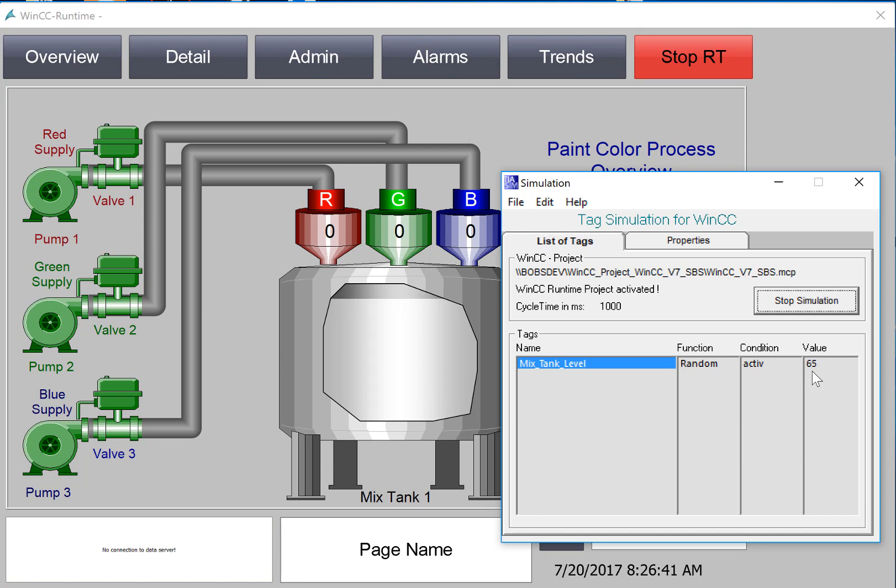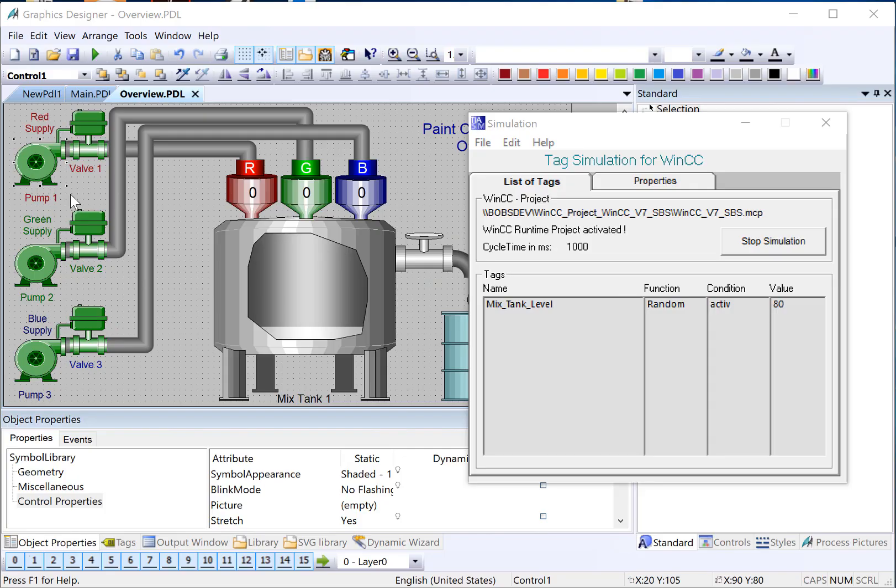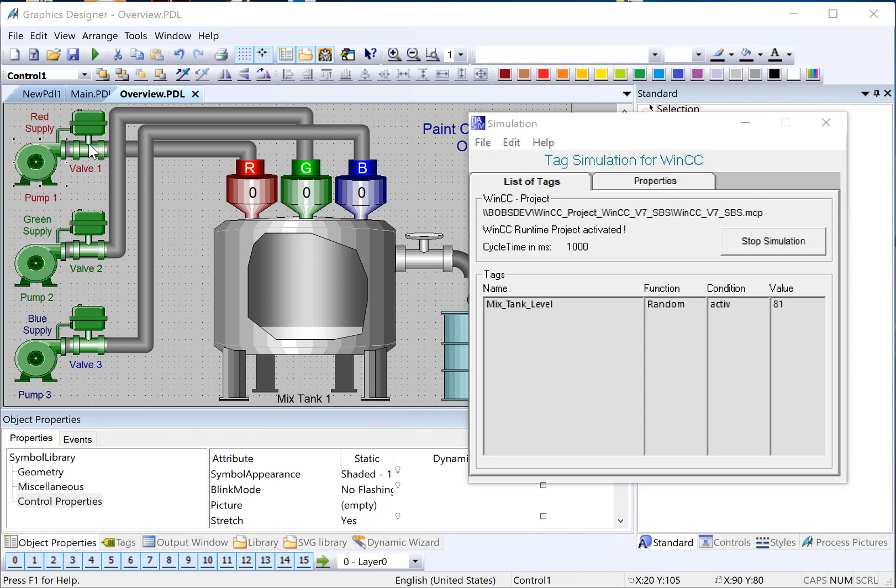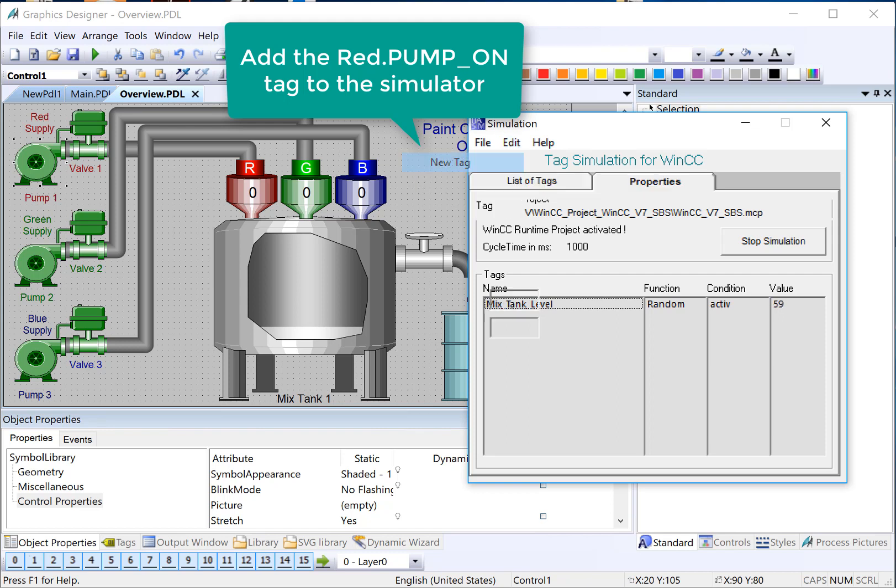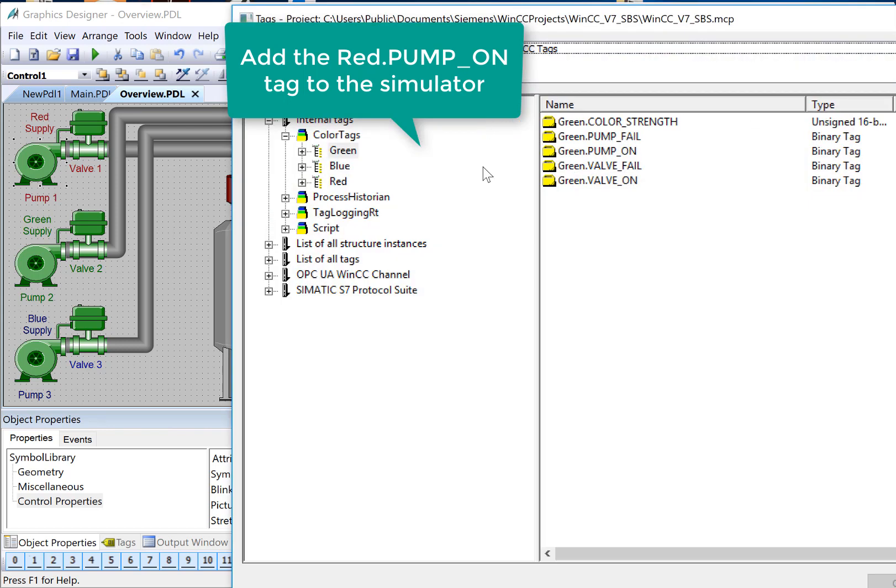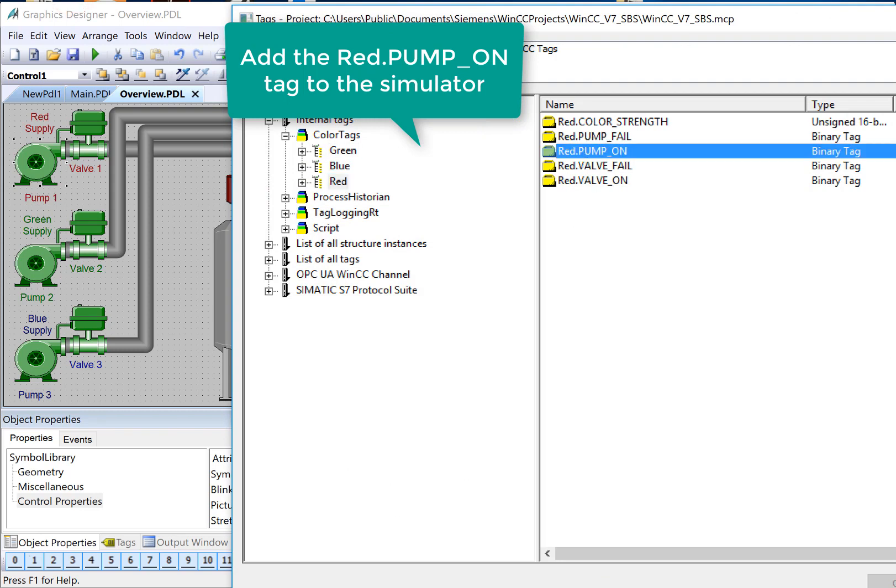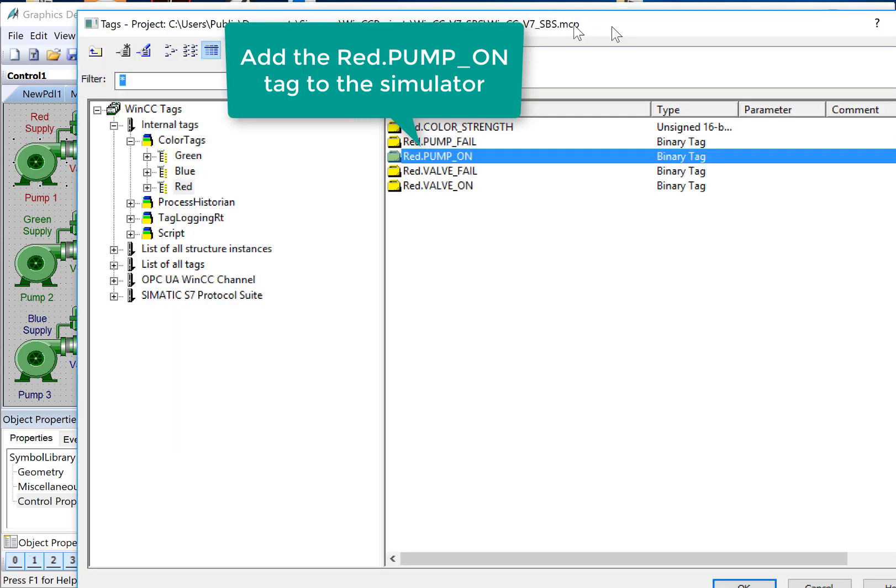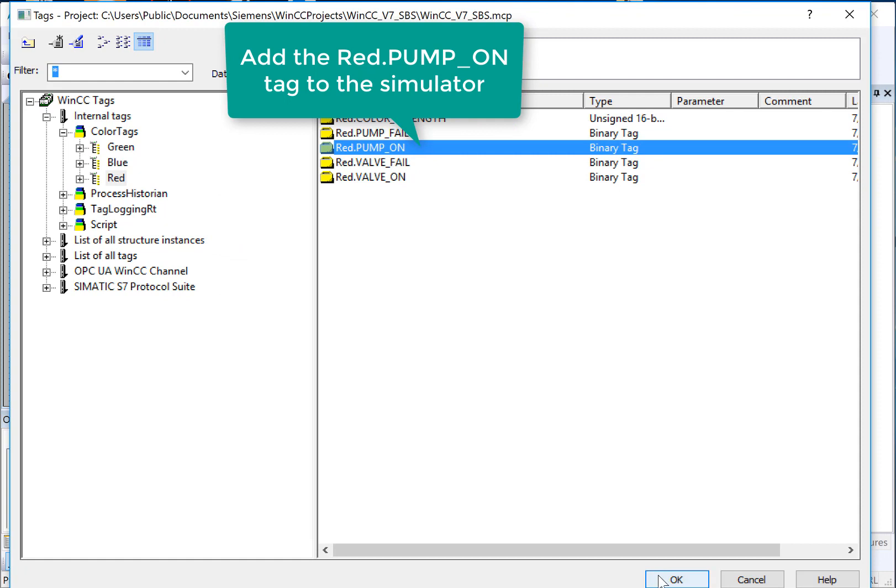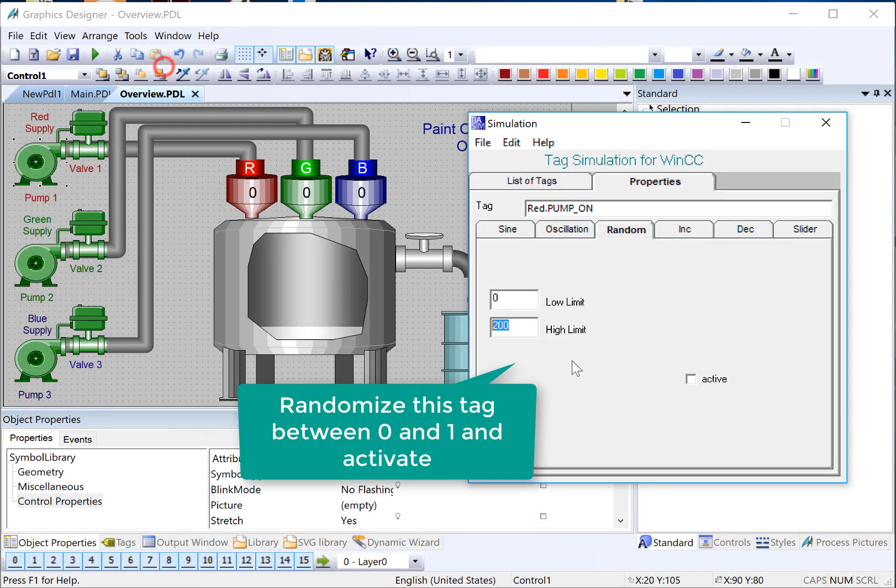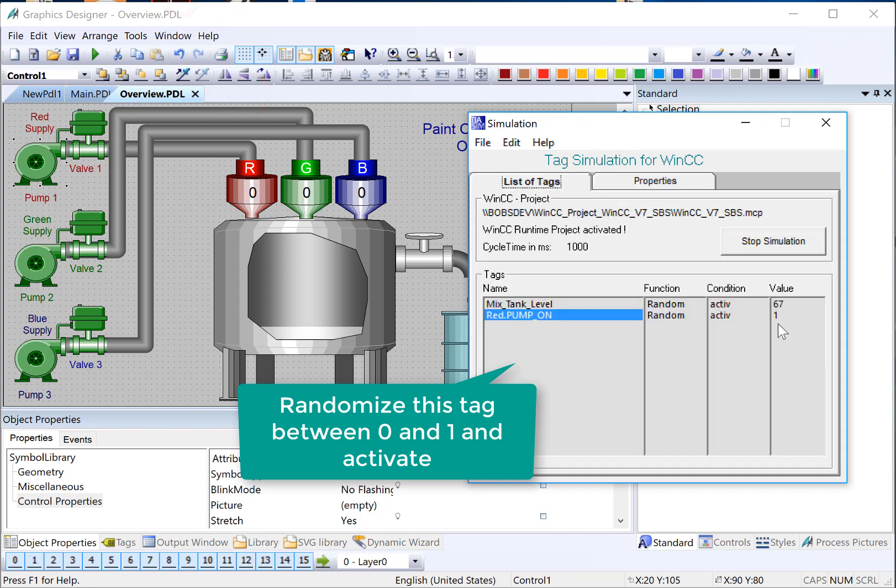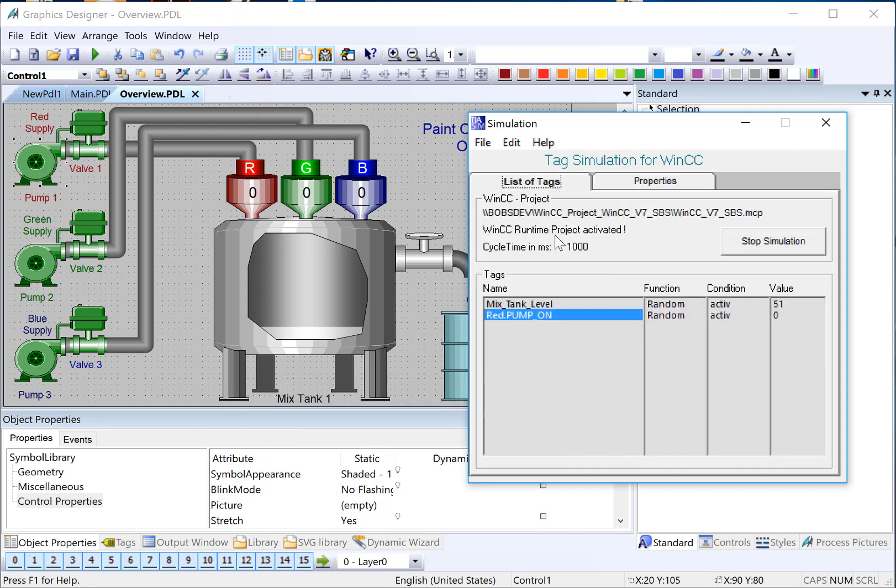Based on the properties that we set, we can see the level is going up and down. Next, let's go ahead and add the tags for our Red Pump, Pump On, Pump Fail, and Valve On to our simulator. And then we'll add the dynamics to change these objects' color based on the states of those tags. So we'll follow the same method that we did to add mix tank level. I'll do Edit New Tag. We'll go to our Red Structure, and we'll choose Red Pump On, and just click OK. And then under Random, we're just going to do 0 1, and choose Active. So we can see it's already simulating.